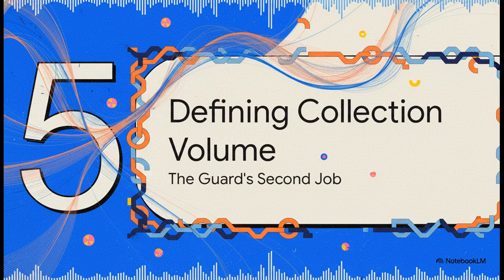We're done, right? Nope, not even close. For a truly accurate measurement, you don't just need a clean signal. You need to know exactly what volume of air that signal came from. And as it turns out, our hero, the guard electrode, has a second, equally important job. See, if you don't have a guard, the electric field gets sloppy. It bulges out at the edges of the collector, kind of like you see here in these diagrams. And that distortion means you're accidentally collecting ions from a region outside your intended measurement volume. So your true collected volume doesn't match your nominal or calculated volume. You think you're measuring a coffee cup's worth of air, but you're really measuring the cup plus a little extra all around it. Your whole measurement is just wrong.